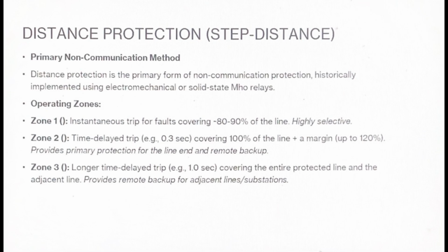For zone 2, this zone covers 100% of the line, plus a margin into the adjacent bus. Because it overreaches, we must add a time delay of around 0.3 seconds to allow the primary protection on the adjacent line to clear the fault first. Zone 2 provides primary protection for the far end of the line and backup for zone 1. Lastly is zone 3. This is your remote backup. It looks even farther down the line and into the next substation. It has a much longer time delay, around 1 second, and is a slow but guaranteed safety net.